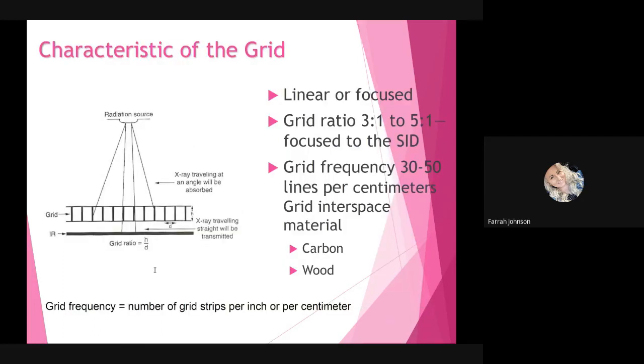So, what are the characteristics of a grid? You can have a linear or focused grid. In a grid ratio, a normal one for mammography is anywhere from 3:1 to 5:1, and it's focused to the SID used. A grid frequency of 30 to 50 lines per centimeter is normal. And the grid interspace material used is either carbon or wood. Note that the grid frequency is the number of grid strips per inch or per centimeter, and your grid ratio is the height of those strips over the distance between them.